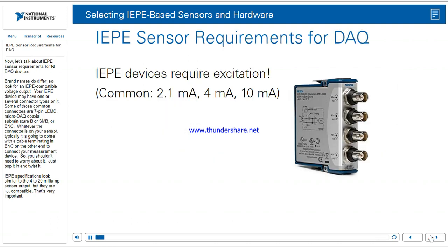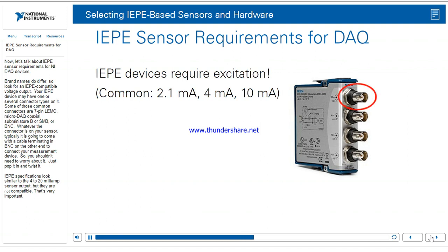Now let's talk about IEPE sensor requirements for NI DAQ devices. Brand names do differ, so look for an IEPE-compatible voltage output. Your IEPE device may have one of several connector types: 7-pin LEMO, micro-dot coaxial, sub-miniature B (SMB), or BNC. Whatever the connector is on your sensor, typically it's going to come with a cable terminating in BNC on the other end to connect to your measurement device — so you shouldn't need to worry about it, just pop it in and twist it. Note that IEPE specifications look similar to the 4 to 20 milliamp sensor output, but they are not compatible — that's very important.